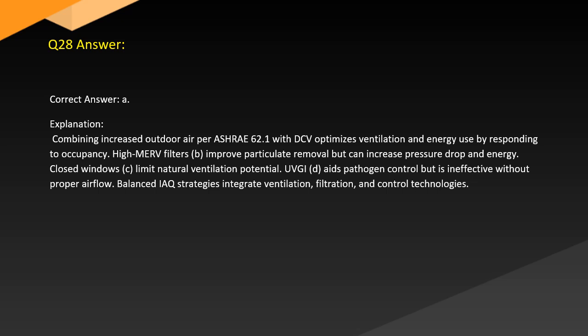Answer. Correct answer A. Explanation. Combining increased outdoor air per ASHRAE 62.1 with DCV optimizes ventilation and energy use by responding to occupancy. High MERV filters, B, improve particulate removal but can increase pressure drop and energy. Closed windows, C, limit natural ventilation potential. UV, D, aids pathogen control but is ineffective without proper airflow. Balanced IAQ strategies integrate ventilation, filtration, and control technologies.